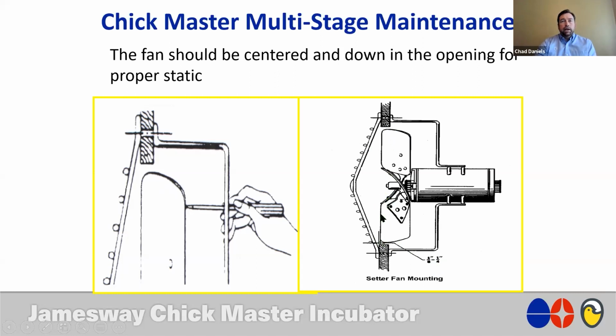I was in a hatchery fairly recently that had gone through and put in all new fan blades, which was great. It was a great step on their part. Unfortunately, they didn't recognize where this needed to be, and the majority of them, the blade was way up out of that opening. So they had lost a lot of static. And the way the story goes is, hey, we put in all brand new blades and we lost 1% in hatch. Well, they didn't put the blades in correctly. So this is important to share with your maintenance staff and make sure they understand where that blade positioning needs to go.